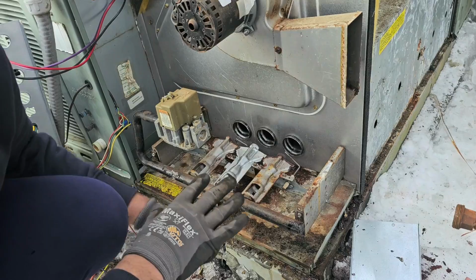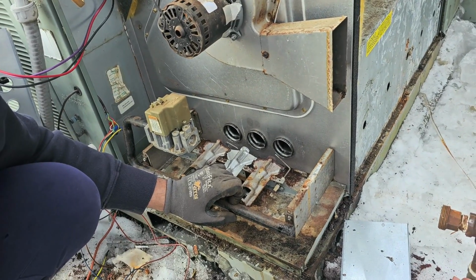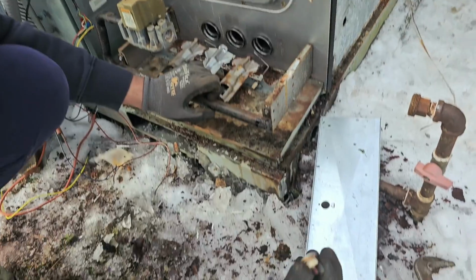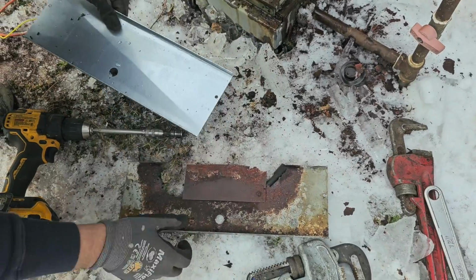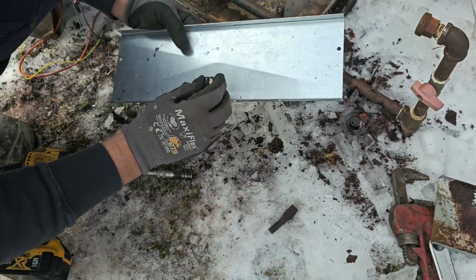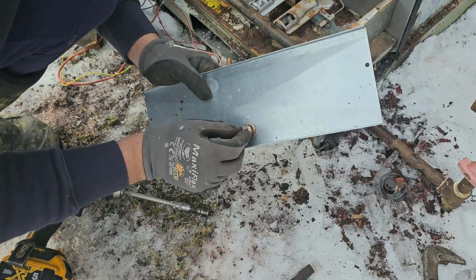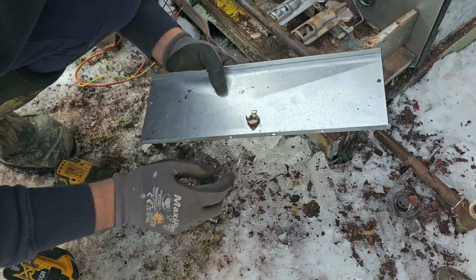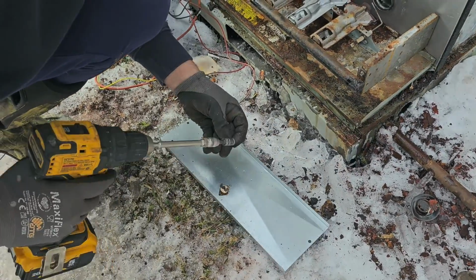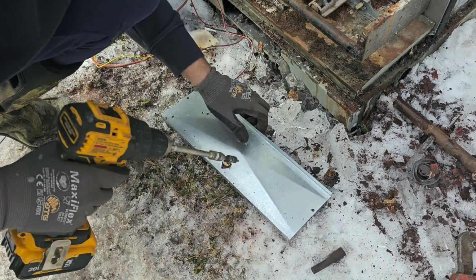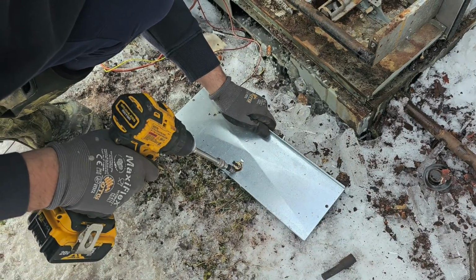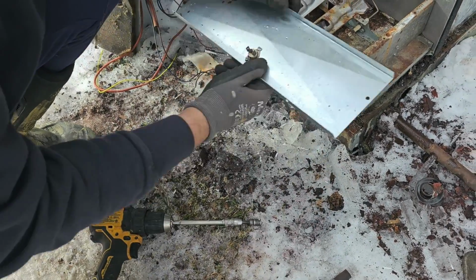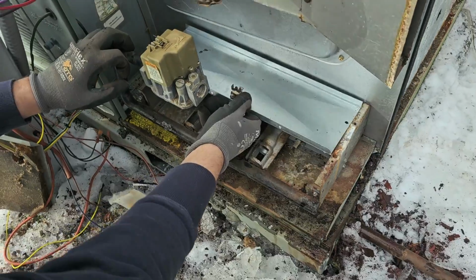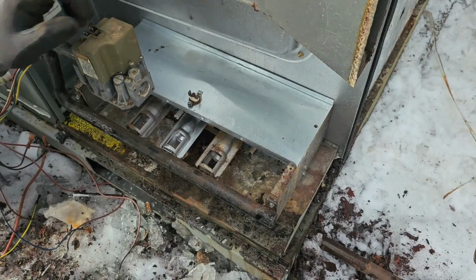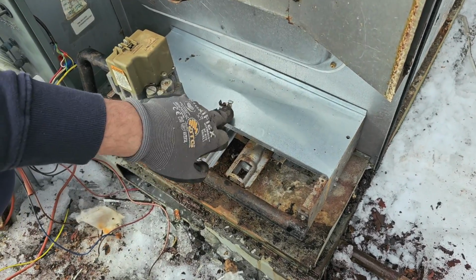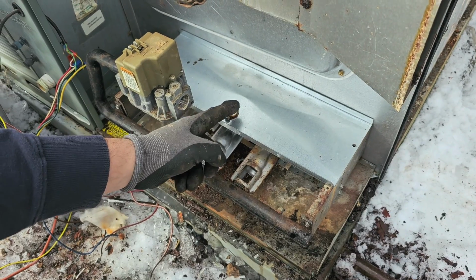All right, now that we've got the manifold pipe attached, we're going to take our rollout switch out of our old plate and put it in our new plate here. See? Doesn't that look a lot better? Like that right there - so that right there is the rollout switch. If the flame rolls out, then that will open up. It's a manual reset.